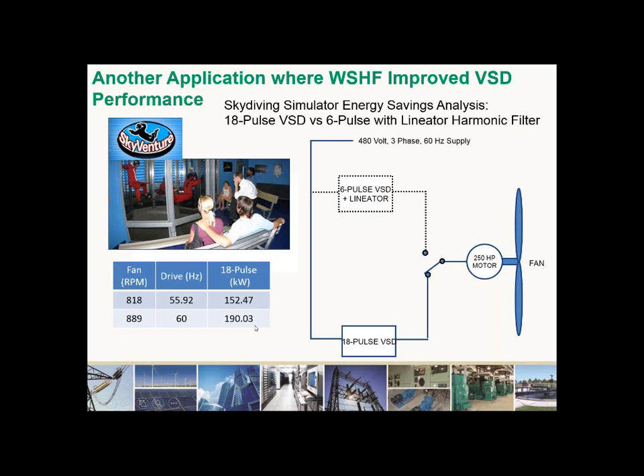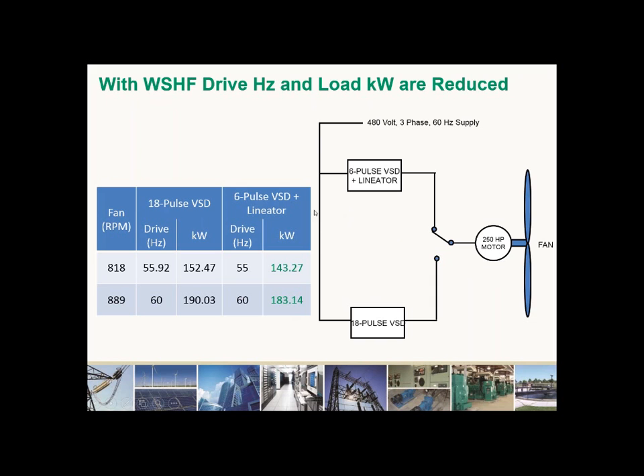On the 18-pulse solution, they were drawing 190 kilowatts. When they reduce the speed to 818 RPM, the drive required just under 56 hertz, and the power consumption dropped to 152. When we switched to the 6-pulse drive and the Lineator, you can see at full speed the power dropped from 190 kilowatts to 183 kilowatts, a substantial reduction with no loss of power output.